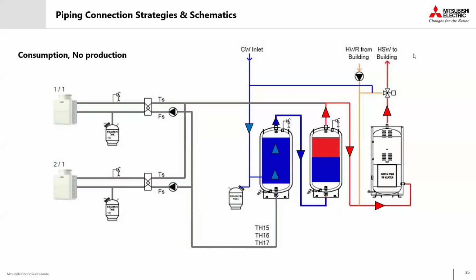So rather than operate the heat pumps right away during that peak demand period, the proper sequence here would be to deplete or draw down that hot water storage from our storage tanks so that we're using as much of that hot stored water as possible. So in this example, our building occupants are using hot water, but the heat pumps have been staged off because they were previously in thermo off, let's say.